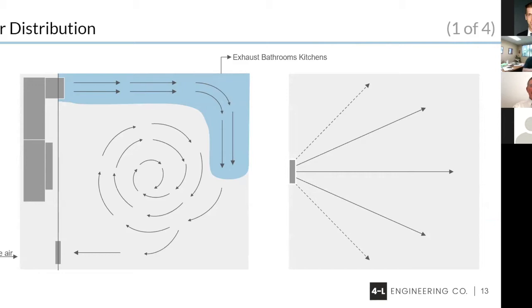Air distribution is a problem. Here we have an air conditioning unit over to our left-hand side in the first slide right there. And we have a filter on the face of it on the lower part that brings the air across the filter into the unit and distributes it through a grill into our room. That would be our primary air that's blowing into the room across the blue area that you see in the picture. As that air moves around, it induces secondary air out of the room, which sort of stirs up some of the particles in the room with your primary air. Then everything moves back to a return grill down at the bottom side. There you'll see that I bring it through a return grill into a sort of boxed-in area, and also mix it with outside air at that point.